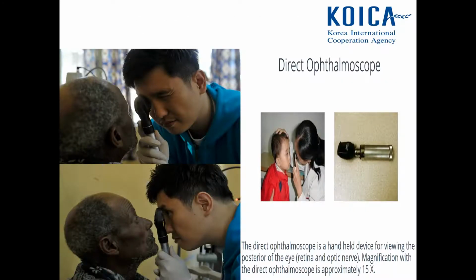There are many types of equipment which help us to watch the retina. The first is the direct ophthalmoscope. It is very light and portable, so it is very useful when we visit a local area to examine those who can hardly visit the hospital. We can evaluate the optic nerve state through this equipment, but it is not easy to watch the whole retinal region because it only shows us an area under 15 degrees. So this is useful when we evaluate glaucoma.